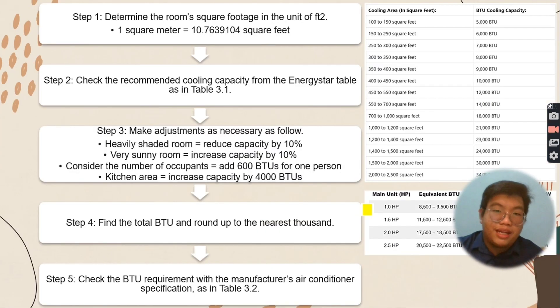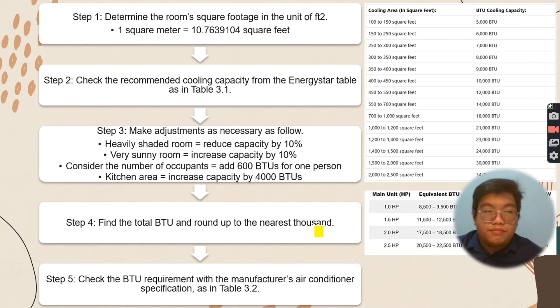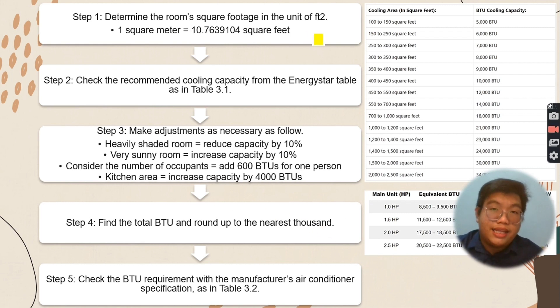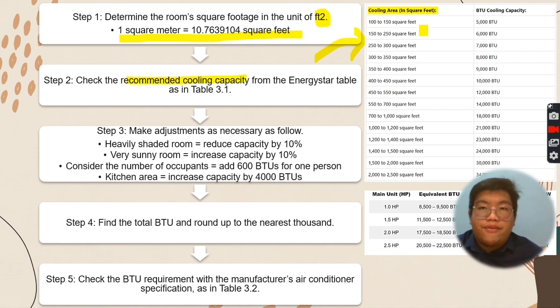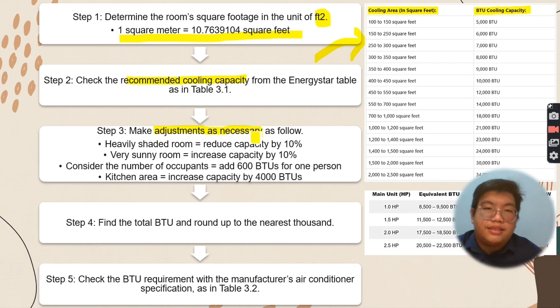Here is the procedure to determine the horsepower needed to install an air conditioner. The first step is to calculate the area of the room in square feet, where one square meter equals 10.76 square feet. After that, we check the recommended cooling capacity by referring to table 3.1, which gives the BTU cooling capacity based on the cooling area in square feet. After that, we make some adjustments as necessary.